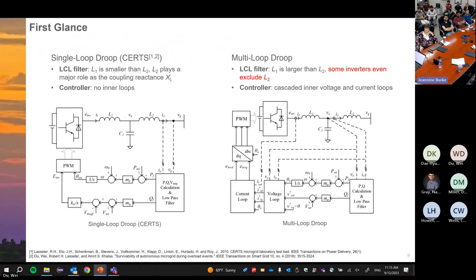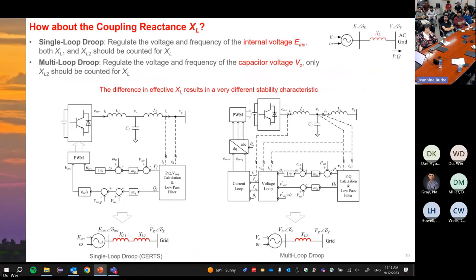The single-loop droop control is simple: PF and QV droop controls generate a phase angle and internal voltage magnitude, directly regulating via PWM — no inner loops. We have an LCL filter with L1 smaller than L2, because we want L2 to play a role as the coupling reactance. For the multi-loop control, they still have an LCL filter, but some literature doesn't even have L2 — only L1 and C1 — and they have cascaded inner voltage and current loops. This is just a quick glance, but to understand it better, we need to ask: where is the voltage source, and where is the coupling reactance XL in each control?